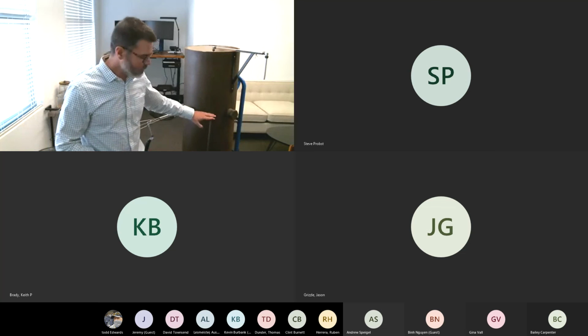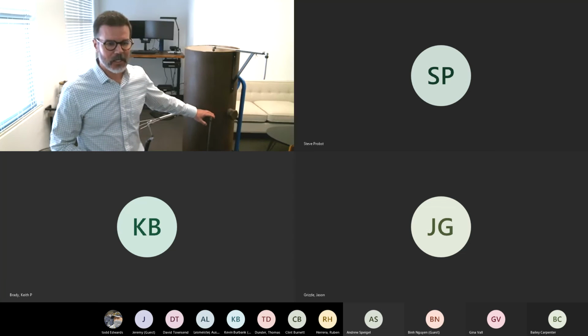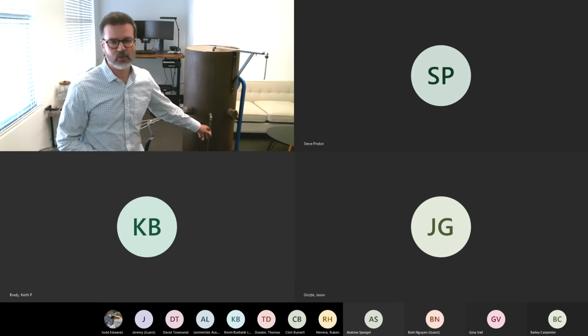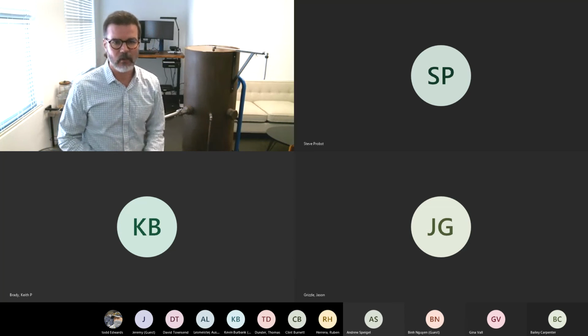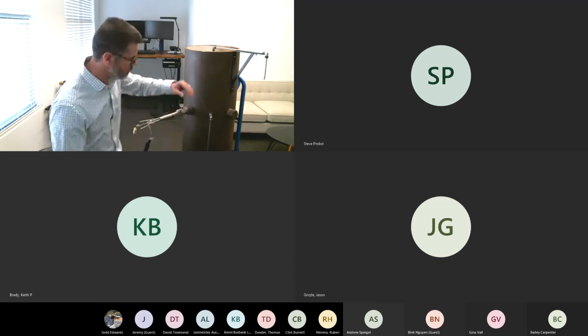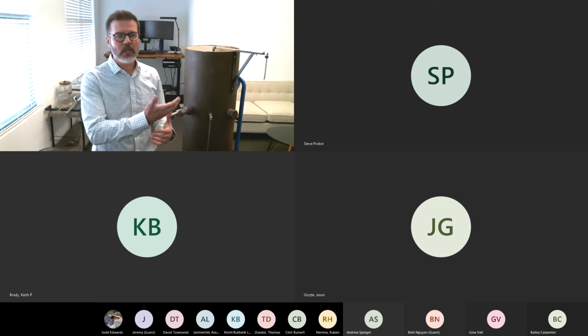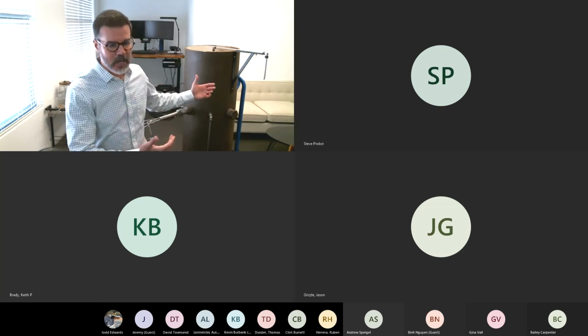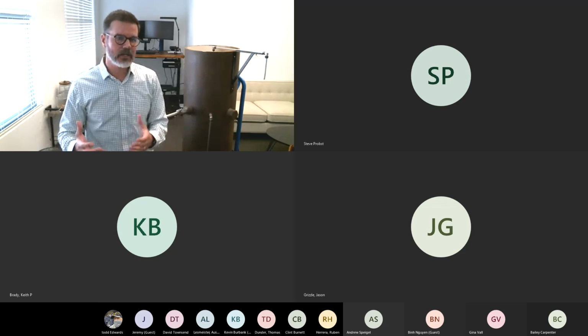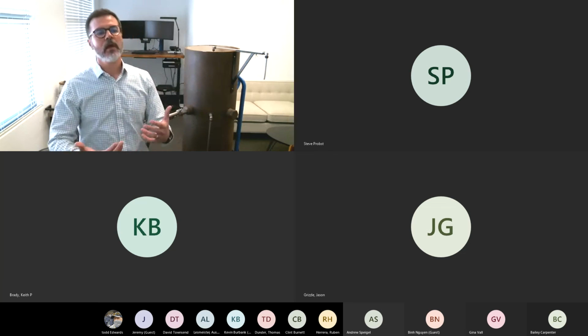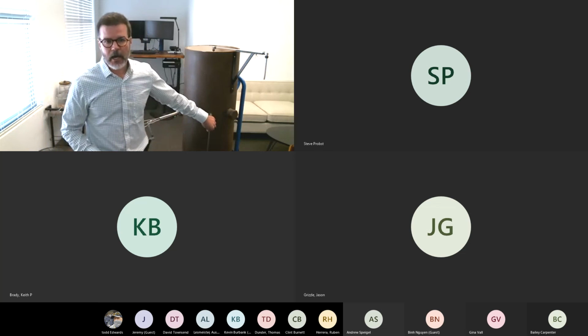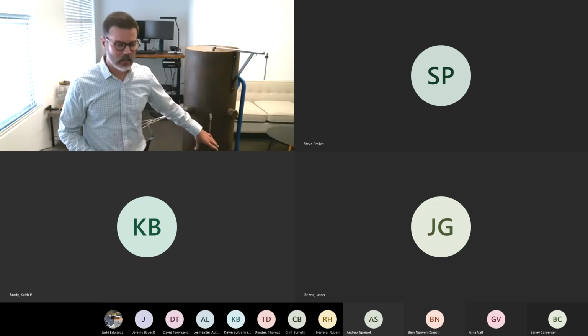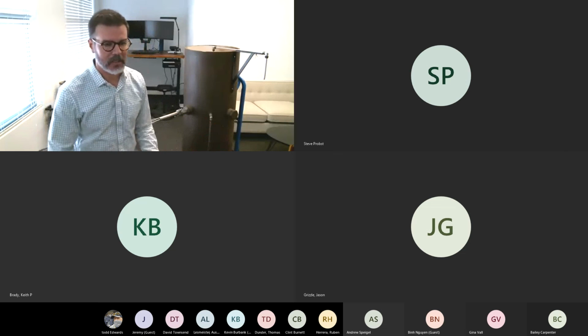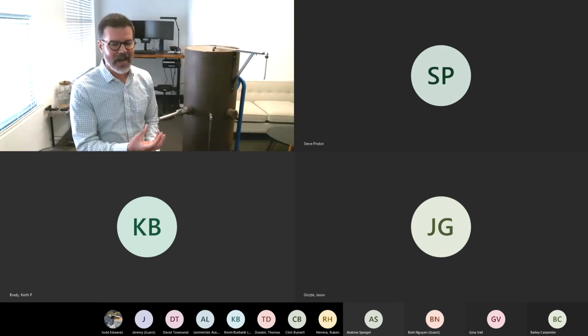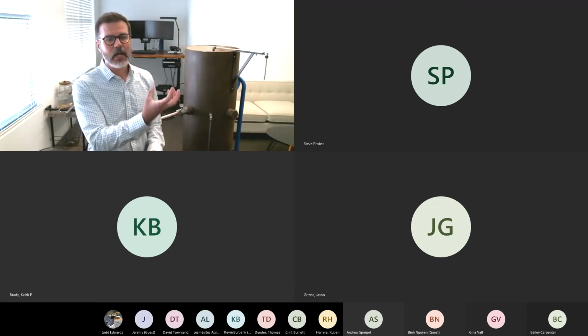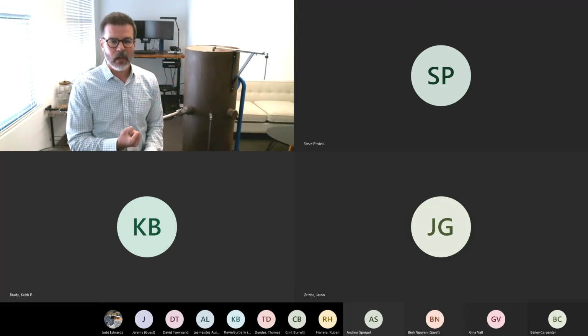And these tubings, the stainless steel drop line, cannot be used for state level or EPA testing. And the reason is the methods would tell us that we need to transport the sample from the stack into our analyzers above the dew point of moisture. What happens when the lines are unheated, when you try to tap into stainless steel tubing like this, moisture condenses within the lines, and once you've got those moisture droplets in there, it starts to strip out your NO2.